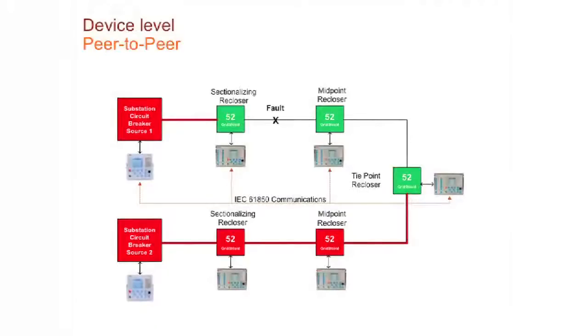Because obviously if you have distributed generation here and you have a fault, and you don't trip that DG, you're going to feed your customers with your distributed generation. So the transfer trip goes from a controller to that device using DNP 3.0. At the same time that it sends that signal to the communication gateway, it also sends a signal via peer-to-peer communication, because it's the same network that they're using. It's the cloud that is just going to a substation gateway.